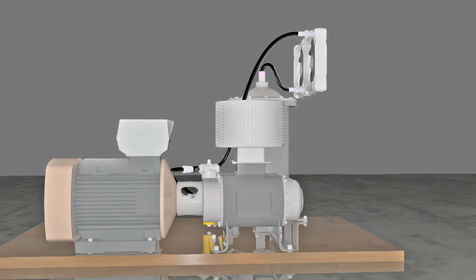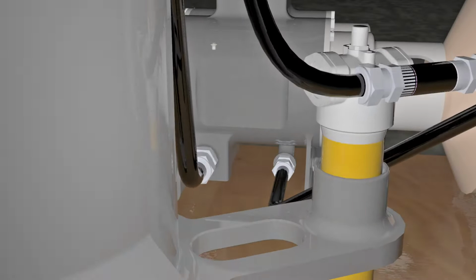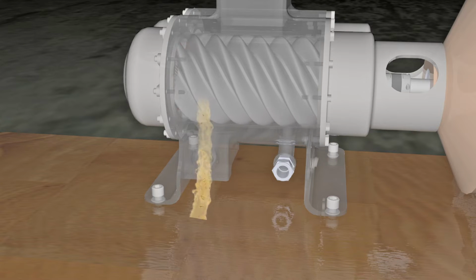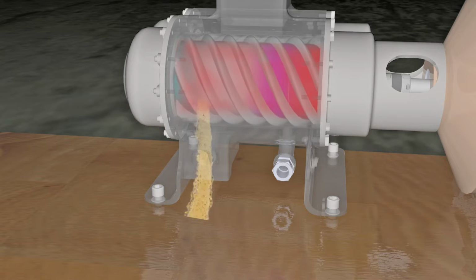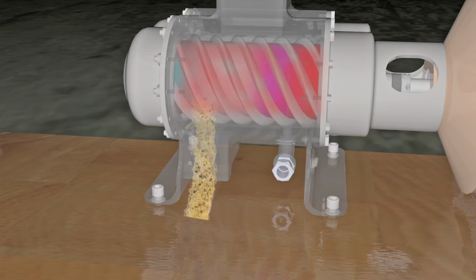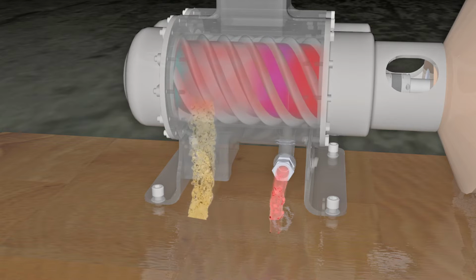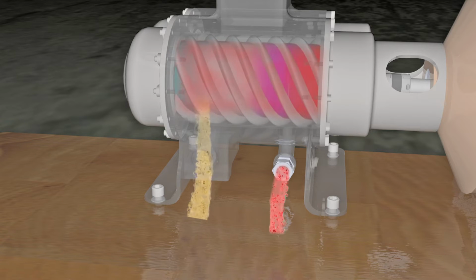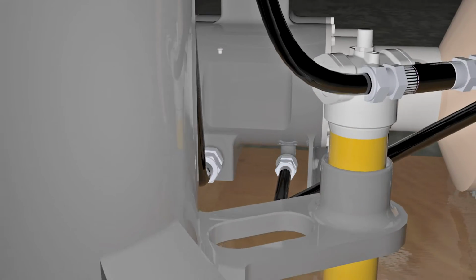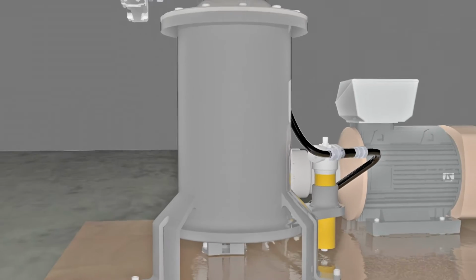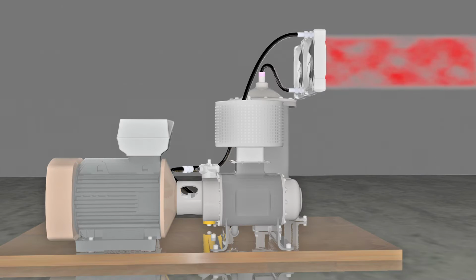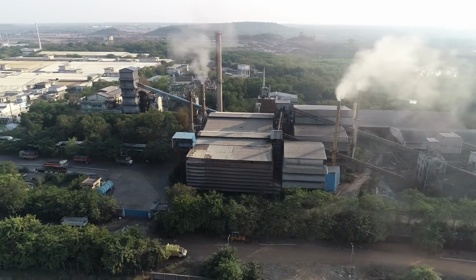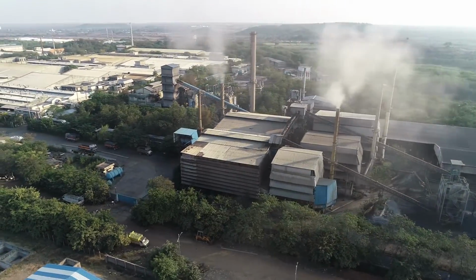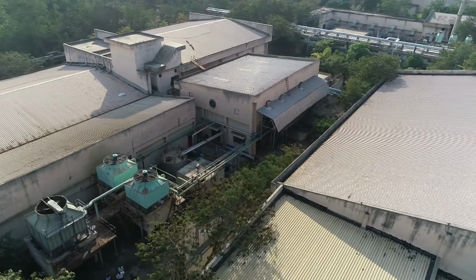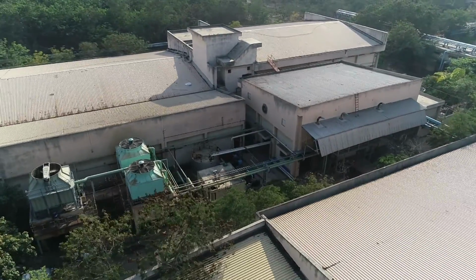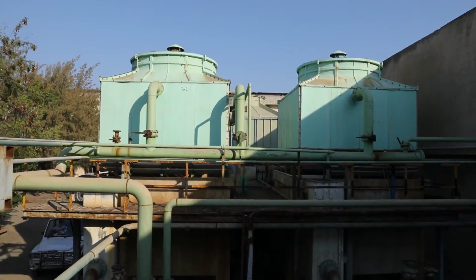The cooling oil used to lubricate the screw element enters through an inlet at 60 to 70 degrees Celsius and gets heated from the heat of the compressor. This mixture of hot oil and air exits through an outlet at 90 to 100 degrees Celsius and flows towards the oil and air separator, and the cooling towers cool the hot oil and air. The hot air gets dissipated into the air. This old mechanism led to significant loss of heat energy and at the same time put a lot of load on the cooling towers as they ended up consuming a lot of energy for regulation of the temperature under desired limits for the process.